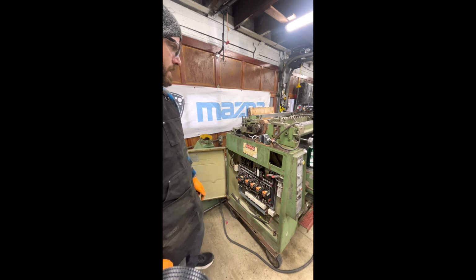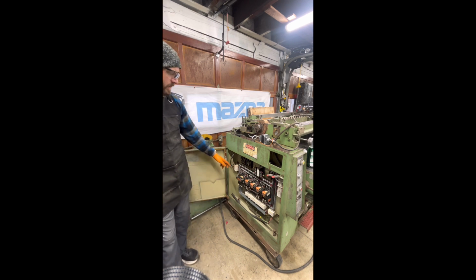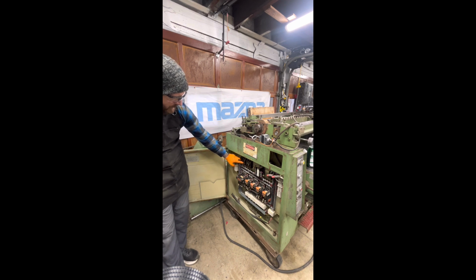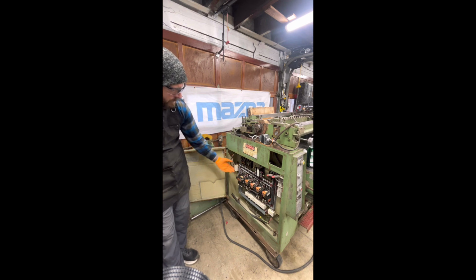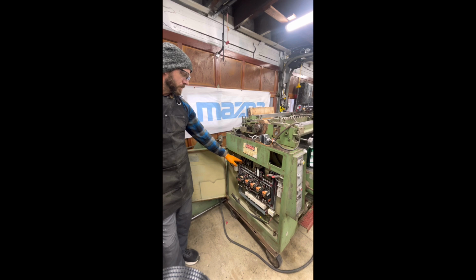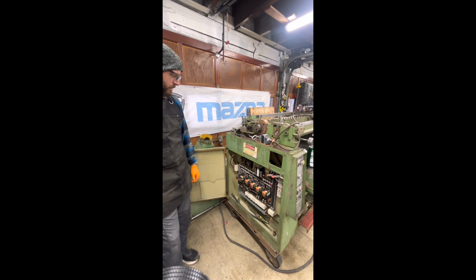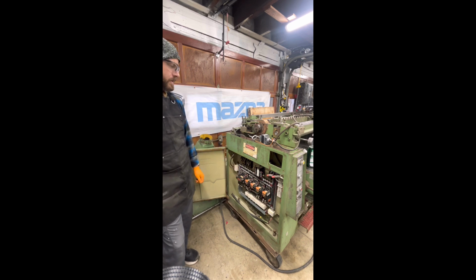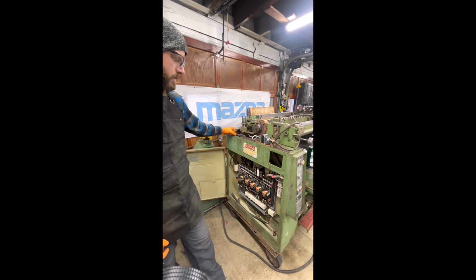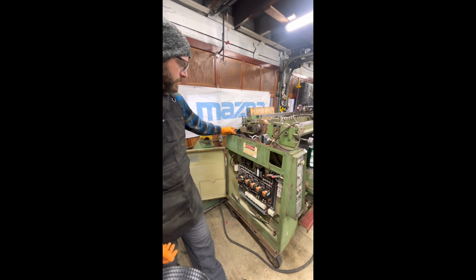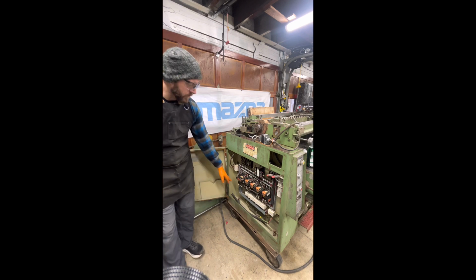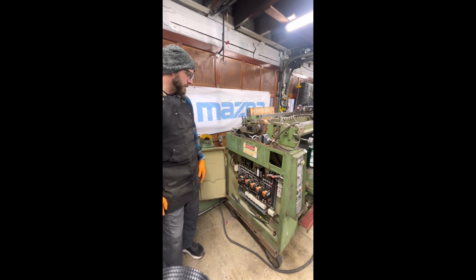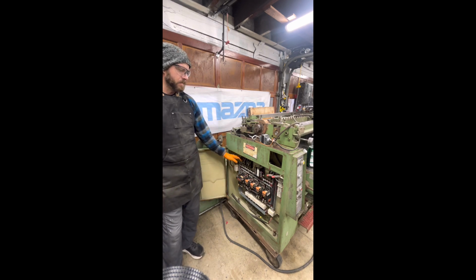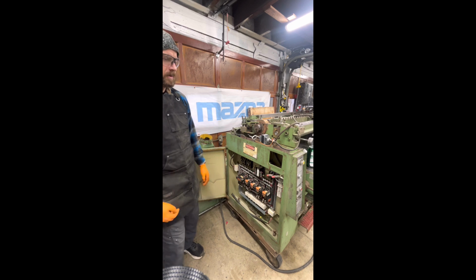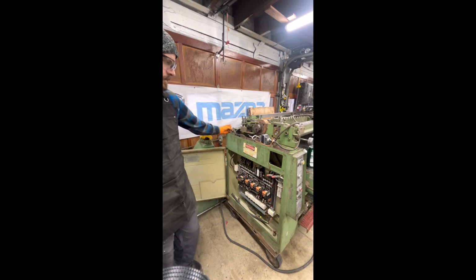The only other major outlier is at some point in its life they bypassed the fuses for the motor protection for the main motor. I plan on pulling these copper jumpers out of there and putting the fuses back in. Not quite sure why they did that — the previous owner I got this unit from was unsure as well. The motor is still protected because you have the overload on the contactor down here, but this is just double protection, more for the circuitry within the building.